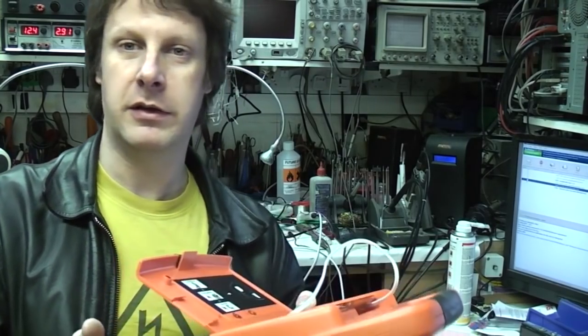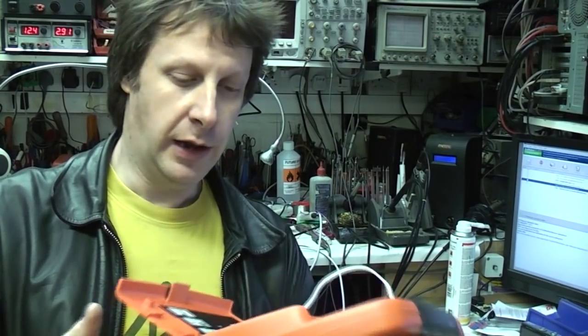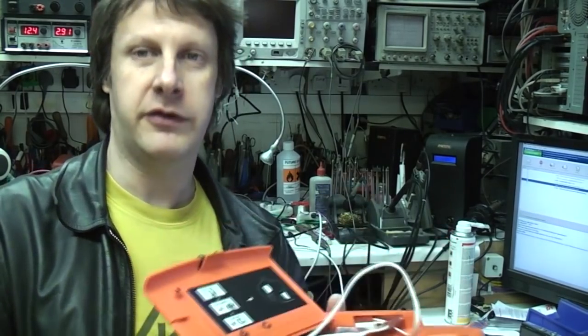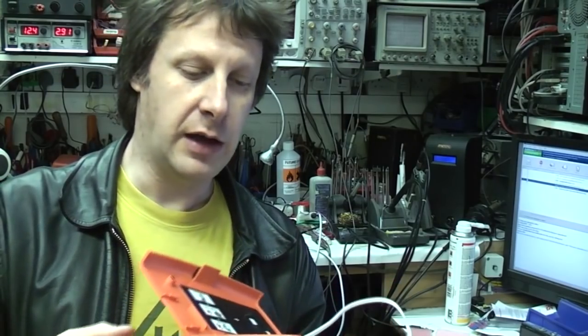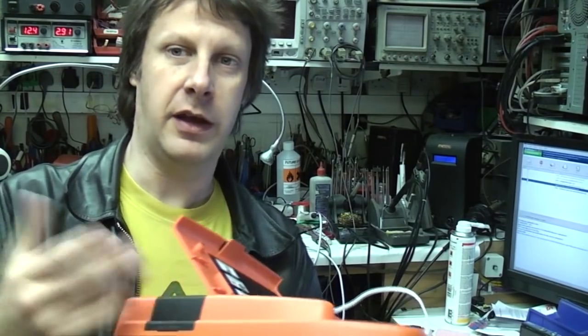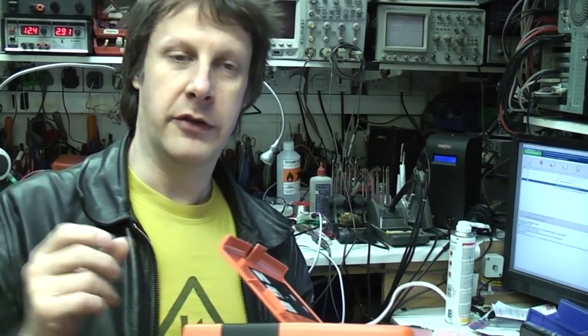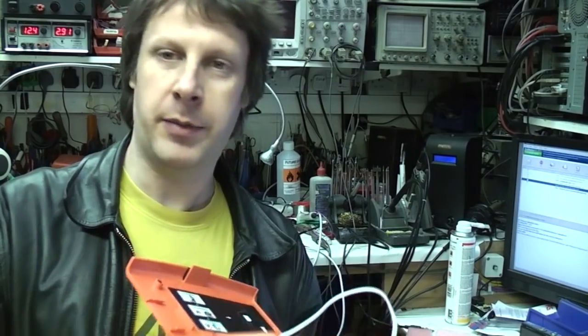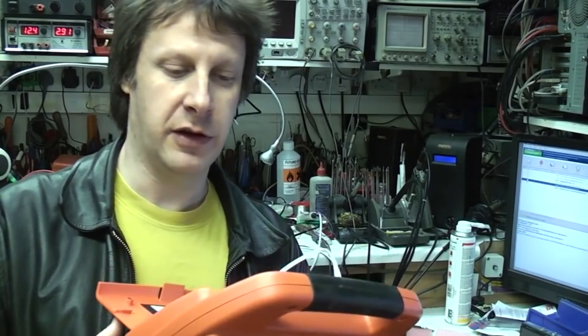The batteries are a non-rechargeable lithium sulfur battery with a five-year life because obviously these things are going to be deployed all over the place. It also does quite extensive self-testing. Every day it switches itself on and does some internal testing, and once a month it actually fully charges its internal capacitors and then discharges them to make sure it's capable of supplying the amount of power needed.